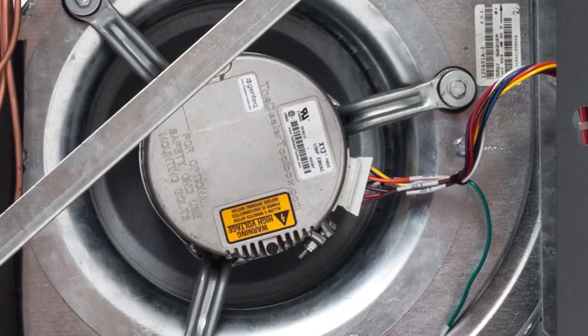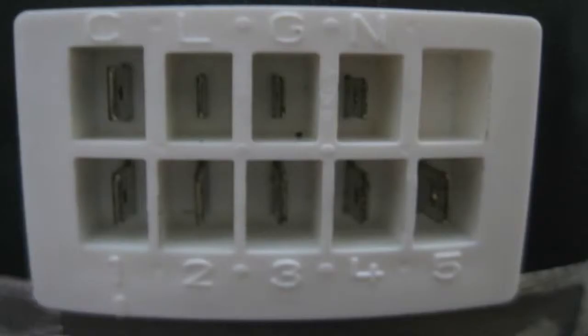There is a connector on the back of the motor that has 4 wires. 2 of those wires provide 230 volts or line volts to the motor at all times, anytime the power is applied to the unit. There is also a 24 volt common and a ground wire. It has up to 5 pre-programmed speed or torque taps labeled 1 through 5.